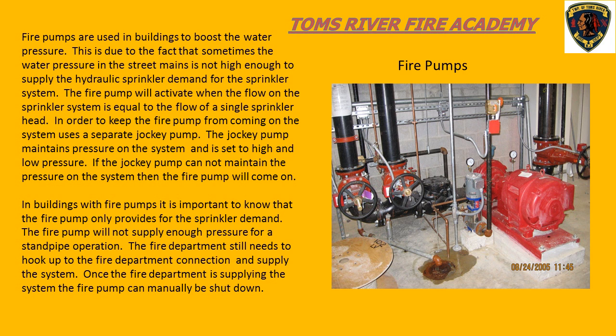One important thing, there are always going to be some pressure fluctuations in the system. So if the pressure starts to dip, we don't want the fire pump coming on. So what they do is they put in a jockey pump. This jockey pump maintains constant pressure on the system until the pressure drops enough, say, from a sprinkler head activation. One sprinkler head activating would cause enough pressure drop to cause the fire pump to come on. So this over here is the fire pump. Very similar to the pumps that we use on our apparatus. This would be the fire pump motor.